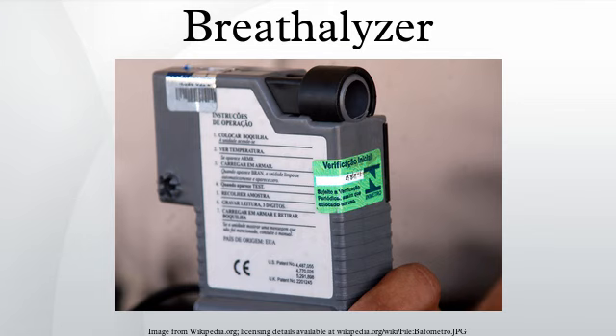The human body is 37 degrees Celsius on average, and breath leaves the mouth at a temperature of 34 degrees Celsius. Alcohol in the body obeys Henry's Law as it is a volatile compound that diffuses in body water. To ensure that variables such as fever and hypothermia could not influence results in a way harmful to the accused, the instrument is calibrated at a ratio of 2100-to-1, underestimating by 9%. Studies suggest that about 1.8% of the population have a partition ratio below 2100-to-1, so a machine using a 2100-to-1 ratio could actually overestimate the BAC.